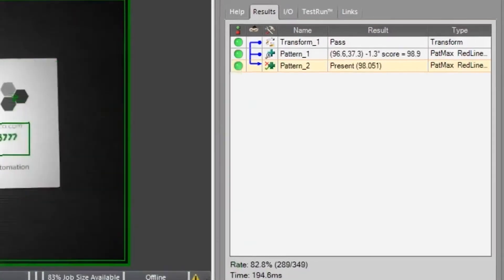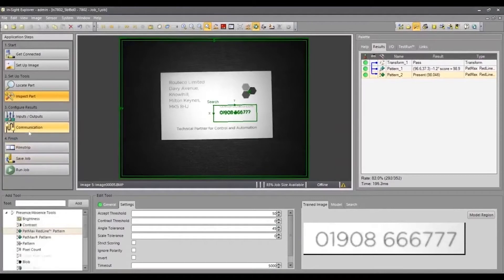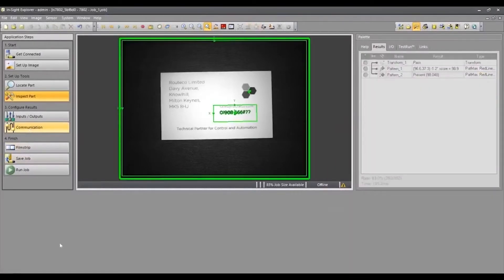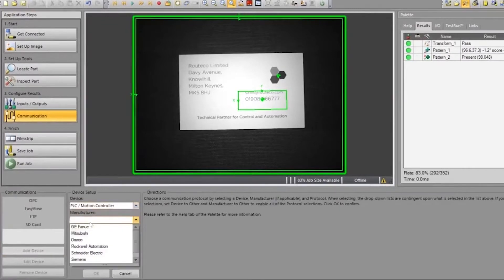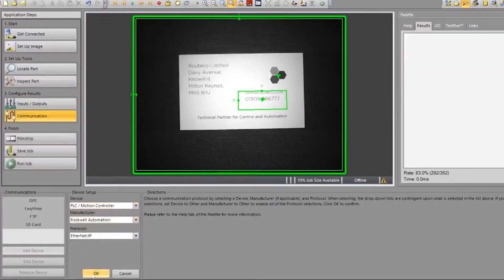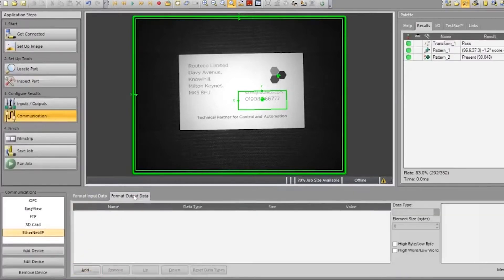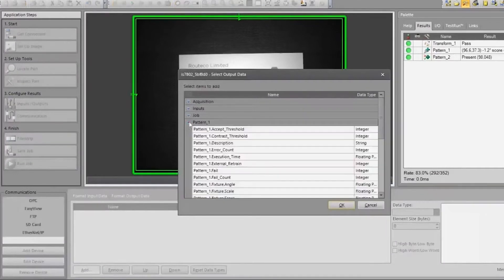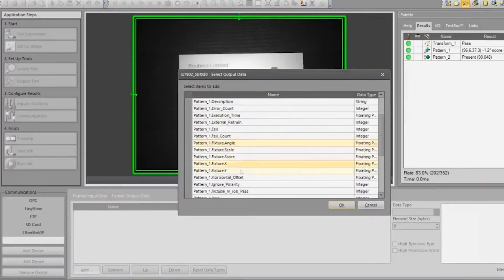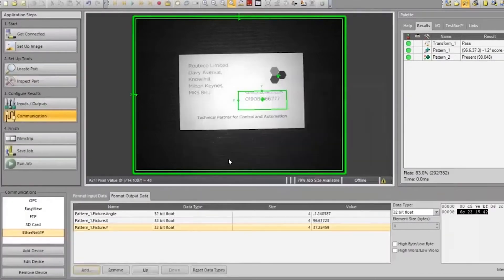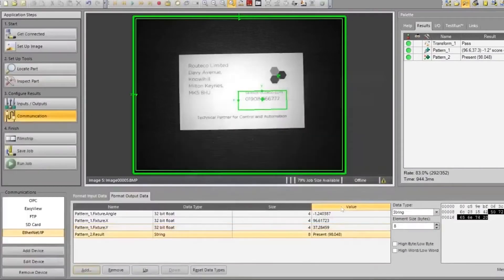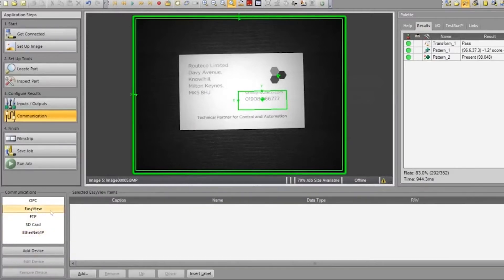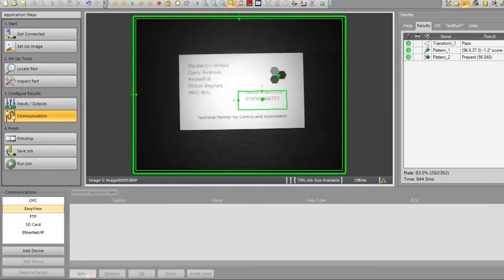Once we are happy with the setup of our job, we then need to set up our communication. Under the communications tab we can select the appropriate PLC we require. The data required into the PLC can be selected from the format output data tab — just by clicking the add button we can choose the information we require. Also under the communication tab, if required, we can set up the EasyView for information out to the PLC.